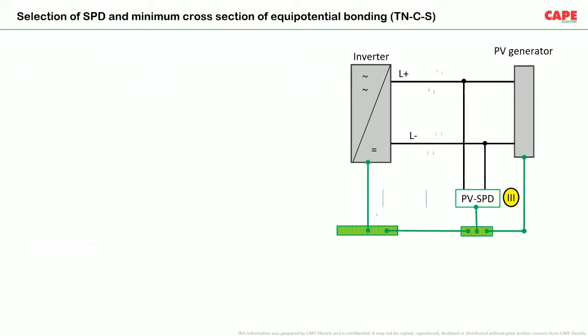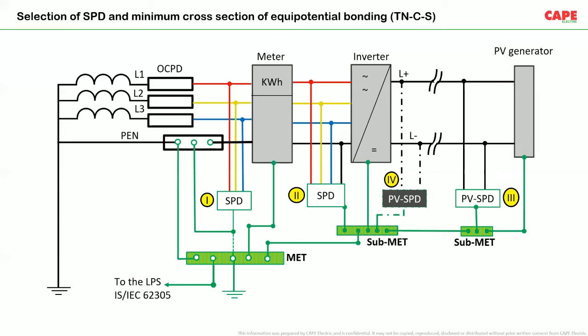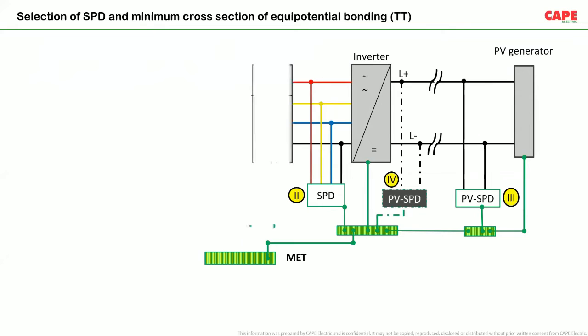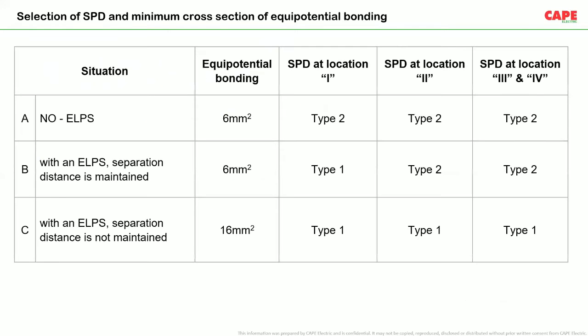Let me skip this particular part. Lightning protection and surge protection, you should not make lightning protection a separate idea and surge protection a separate idea. No, both have to be combined in such a way that, depending upon the type of lightning protection, you should select the wiring. The size of the wiring and the type of SPD shall be selected based on whether you have an external lightning protection system or not.